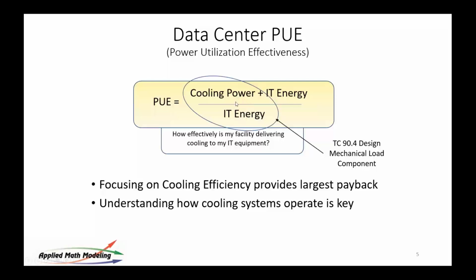So now we're getting a good look at, now this is very much like when you see a chiller efficiency, which typically is measured in kilowatts per ton, which is a crazy series of numbers because they're not unitless. But it's the same idea, except it's for the entire system. It is the amount of energy that we're using to cool the data center, including everything.